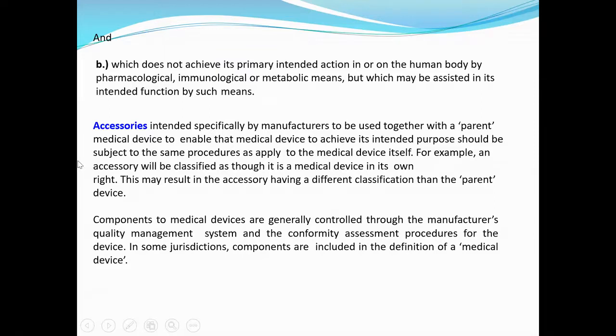Then medical device accessories. Some accessories could also be used as medical devices. Accessories intended specifically by the manufacturer to be used together with a parent medical device to enable that device to achieve its intended purpose should be subject to the same procedure as applied to the medical device itself. For example, an accessory will be classified as though it is a medical device in its own right. This may result in the accessory having a different classification than the parent device. You must have seen the inhalers used for asthmatic patients. Some accessories are used to inhale with the pump, and other accessories are used to inhale the medicine. So those kinds of medical devices come under this category.